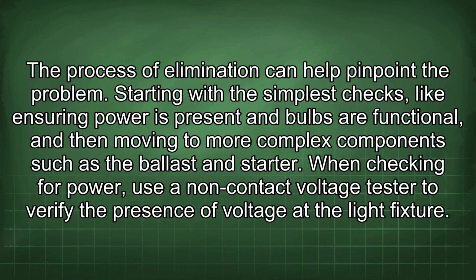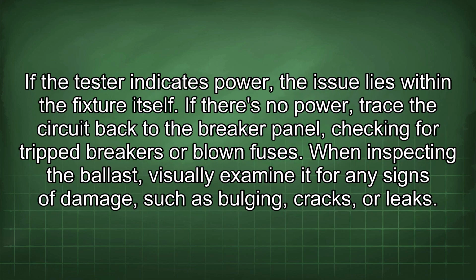The process of elimination can help pinpoint the problem. Starting with the simplest checks, like ensuring power is present and bulbs are functional, and then moving to more complex components such as the ballast and starter. When checking for power, use a non-contact voltage tester to verify the presence of voltage at the light fixture. If the tester indicates power, the issue lies within the fixture itself.